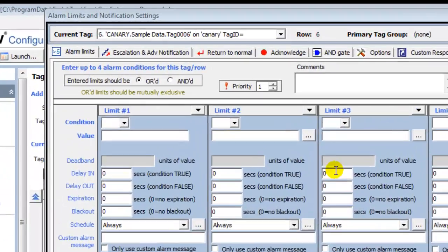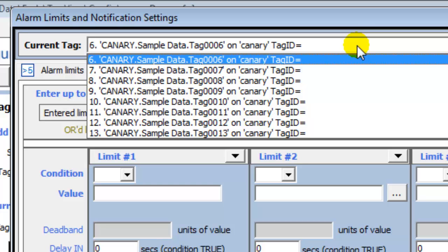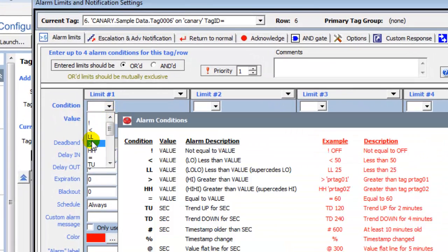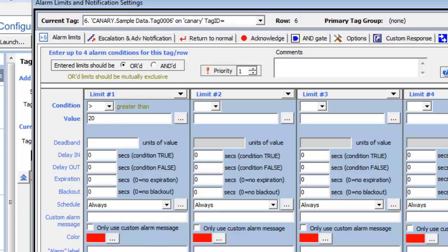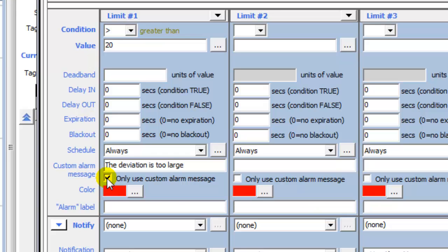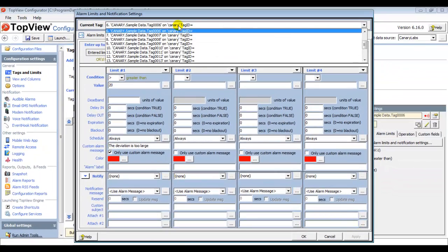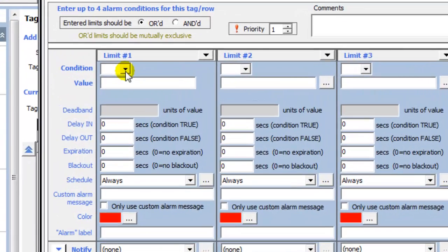The top of the Alarm Limits screen contains a drop-down of the monitored tags. As you configure the limits and notification settings, you are doing so for the selected tag. I'm going to make sure that my sixth tag, the deviation tag, is selected. Each monitored tag can have four alarm conditions. For the deviation tag, I'm going to set the alarm condition to greater than 20. I will also enter a custom message that the deviation is too large, and check the box to only show the custom alarm message. Next, I'll click Apply and select my first tag, the Flow Tag. For the Flow Tag, I will enter an alarm condition greater than 1500 and set the delay in to 10 seconds. An alarm for this tag will occur if the value goes above 1500 and remains there for 10 seconds.